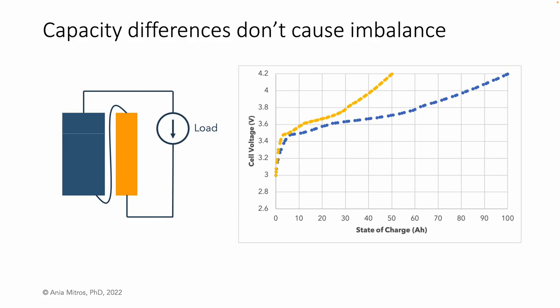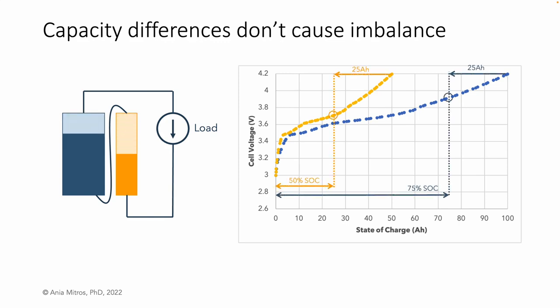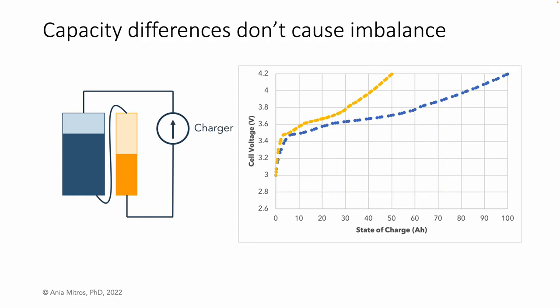As we discharge, the cell voltages deviate. When the smaller capacity cell is at 50%, the higher capacity cell is still at 75%. If all we look at is voltage, it appears we have an imbalance, but we don't—the residual charge capacities of these two cells are identical. When we charge again, the two cells reach top of charge concurrently.